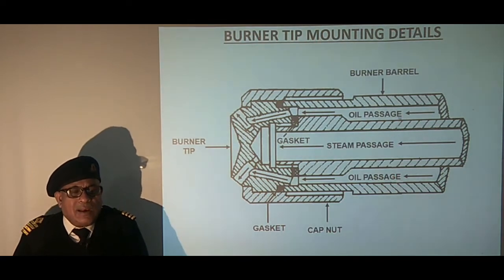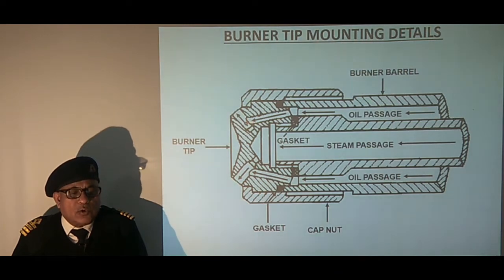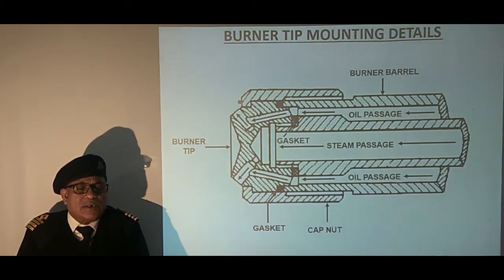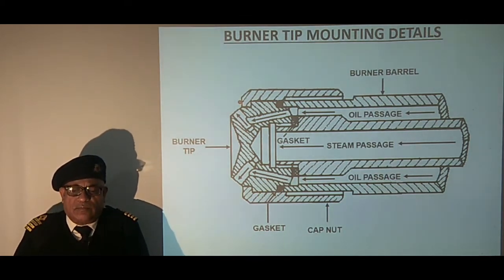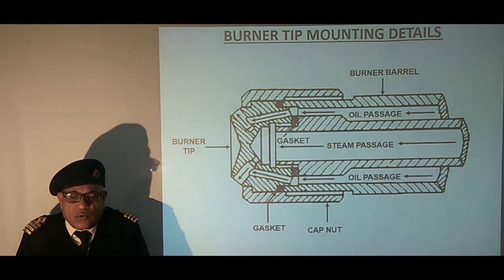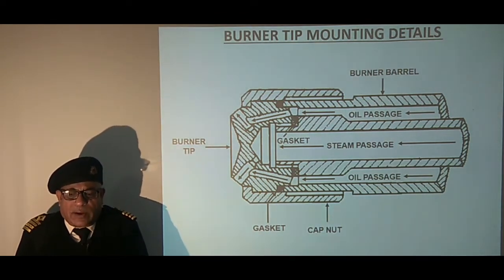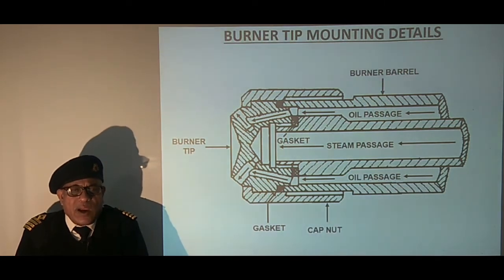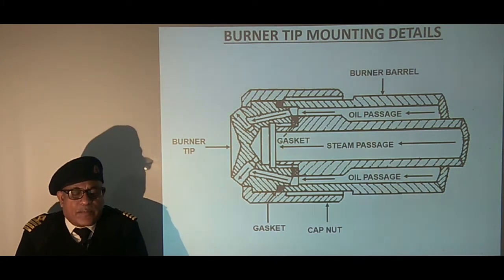The oil enters through the outer channel and goes into the nozzle where steam has already acquired high velocity, and is discharged into the furnace where it mixes with the surrounding air. This burner has a high turn down ratio of 20 to 1 and is thus able to provide a wide operating range at various loads. In comparison to the pressure jet burner, its flame is not so well defined.